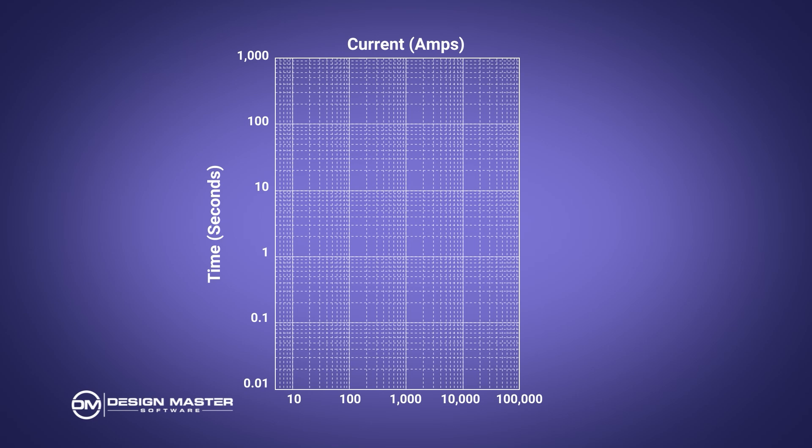Not all curves for all fuses that exist are published. Sometimes the manufacturer will publish a few curves, and the official way to handle the others is to interpolate between the provided curves. So if they give you a 50-amp curve and a 100-amp curve and you have a 60-amp fuse, you put a curve in between and figure out what it looks like. That's not something you really want to do by hand, but when you have software where the curves are digitized, it's a bit easier to figure out.